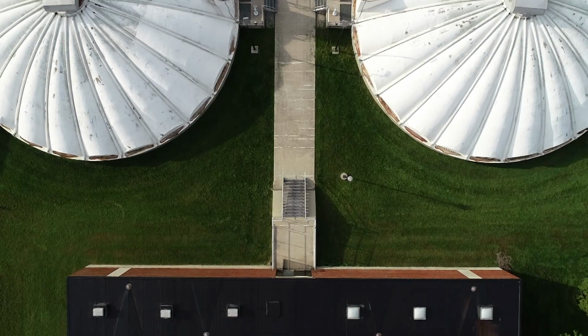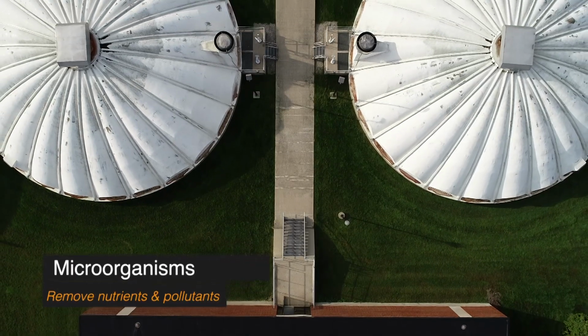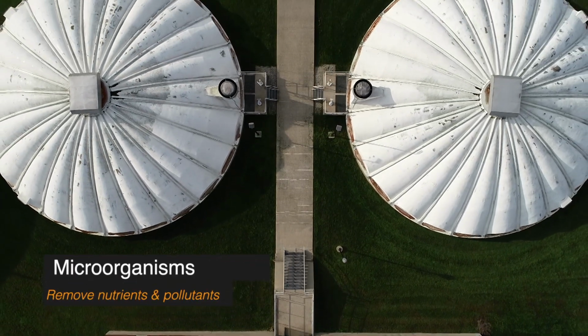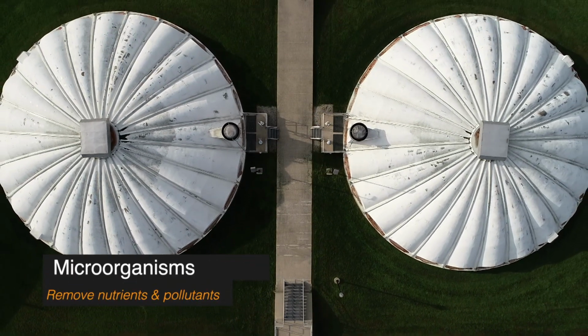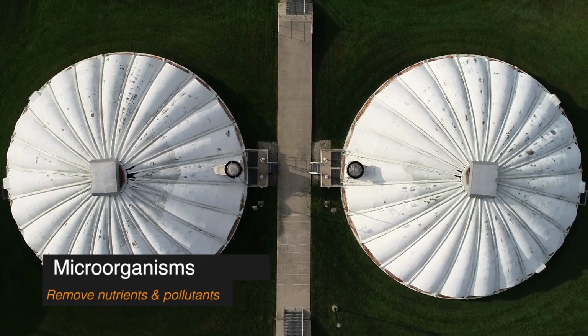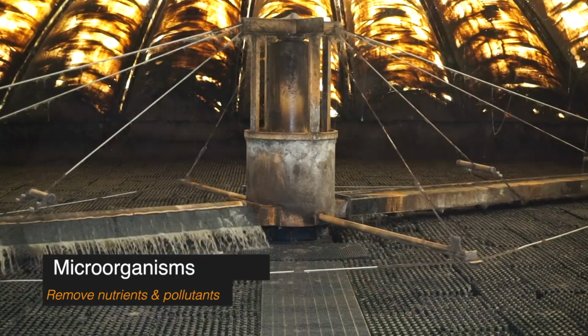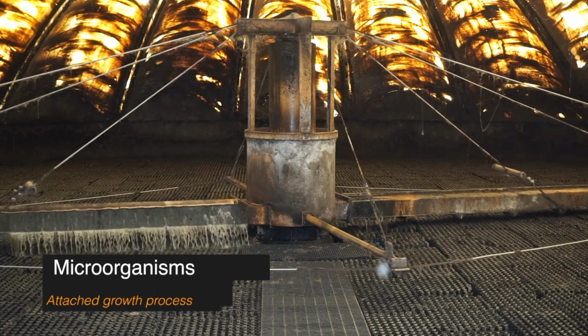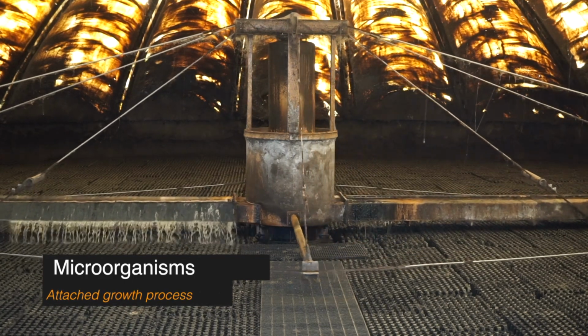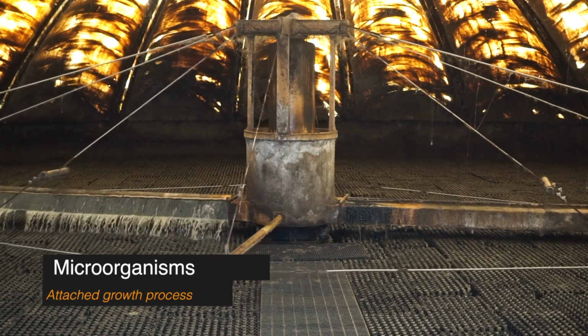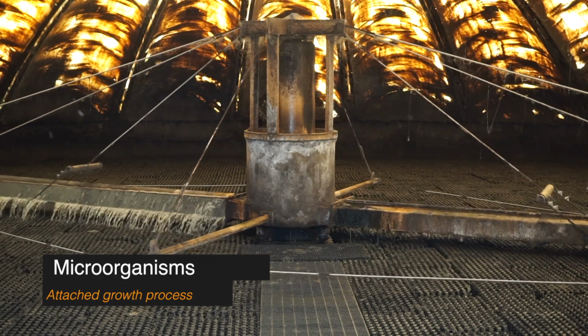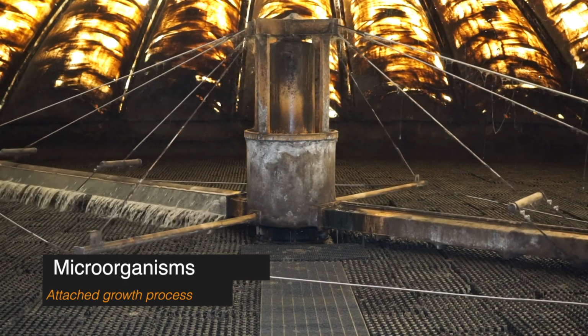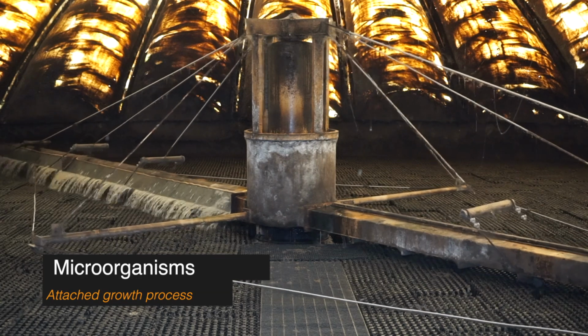The next step in the process is the trickling filters. This is the biological portion of the treatment process. In here, we utilize microorganisms that grow on the surface of honeycomb-shaped media to remove nutrients and pollutants. The wastewater is distributed across the filter and trickles through the media to the bottom of the tank. This keeps the surface wet at all times.